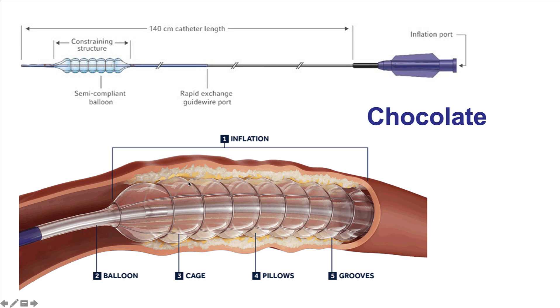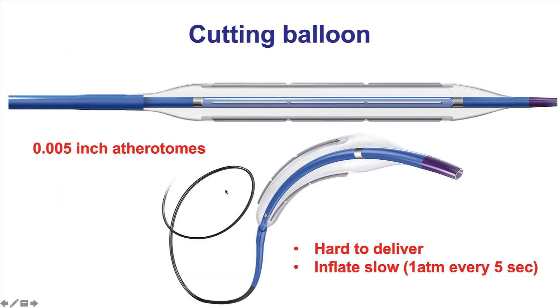The cutting balloon has small atherotomes embedded into it. What is special about this balloon is that it is hard to deliver, and when you do deliver it, you want to inflate very slowly — one atmosphere every five seconds — to allow enough time for the balloon to unwrap, and also when deflated, allow enough time for the balloon to rewrap without damaging it. It can provide good modification of the lesion. All of these plaque modification balloons are less likely to have the watermelon seeding effect because the atherotomes or the wires around the balloon minimize balloon movement and anchor the balloon against the plaque.